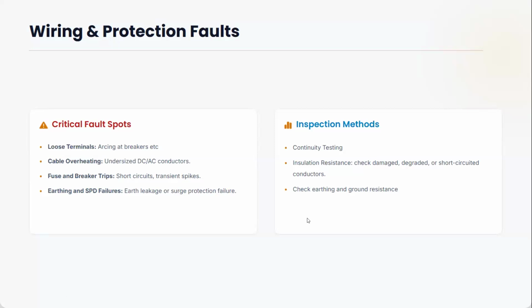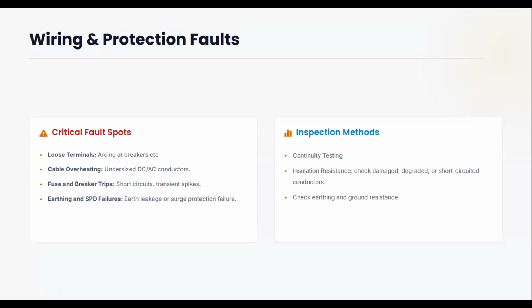Inspection methods: continuity testing. This is where you test cables and breakers. You switch it on, you check at the other end. Is it continuous? Is it continuous from the source to the inverter? If it's the inverter, you check all the wiring between the two points, and whether the components in between are working well. Is there a connection between the two ends of the cable? So we check all that. That's continuity. That's bypass switches. You do this continuity test on all breakers, fuses, and all that.